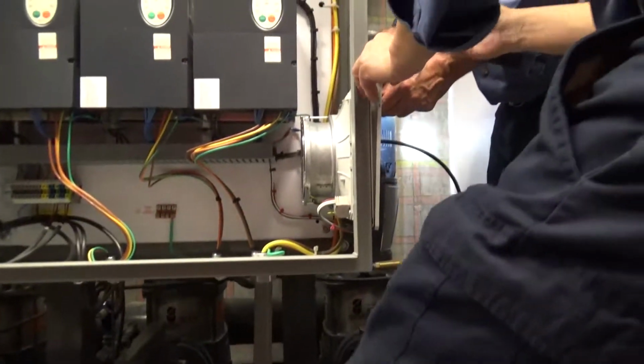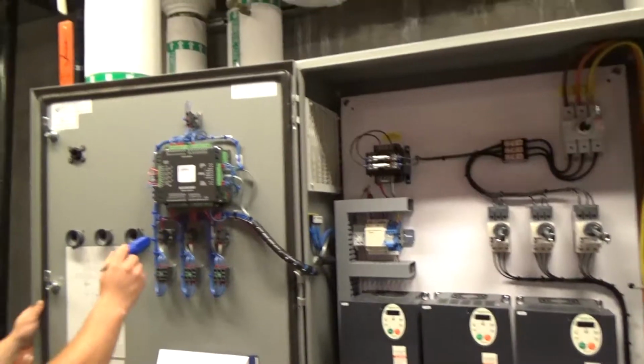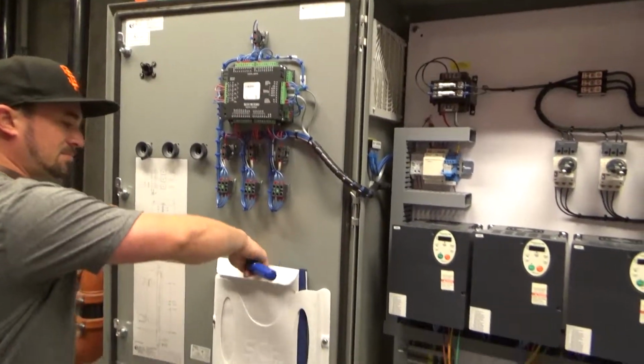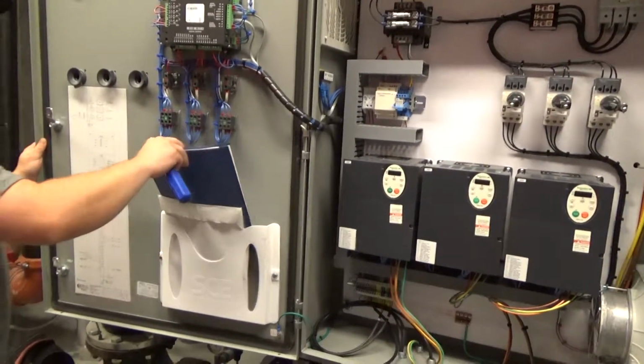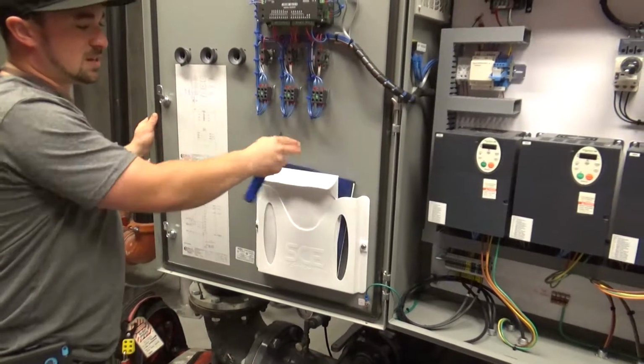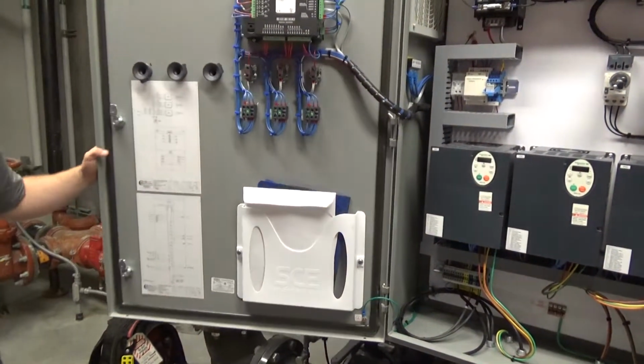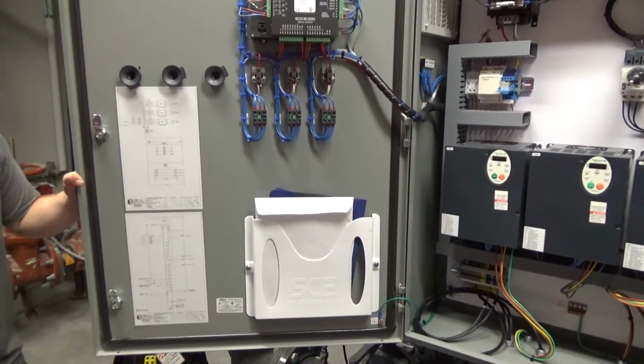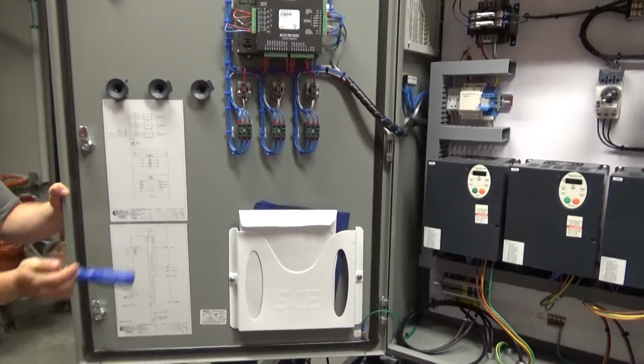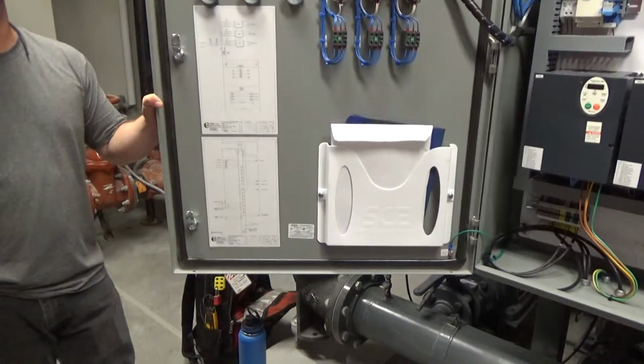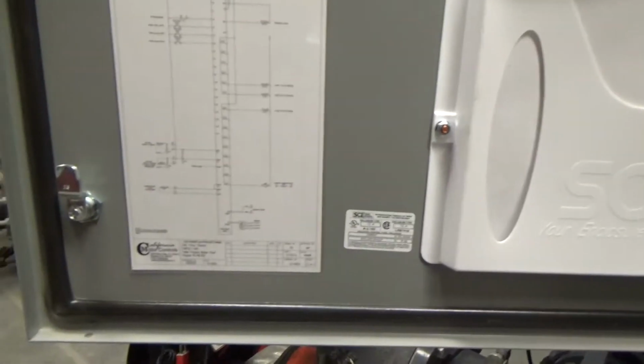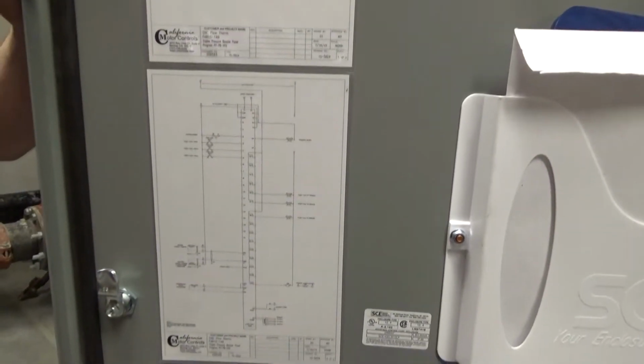And this is your PLC right here. This is back your PLC with all your switches and such. Blue manual. This is that IO&M I was talking about. We always keep it in there, but if you guys want to keep it in the engineering office, you can do that too. And wiring diagram for troubleshooting, anything like that. So very helpful if you're trying to troubleshoot.